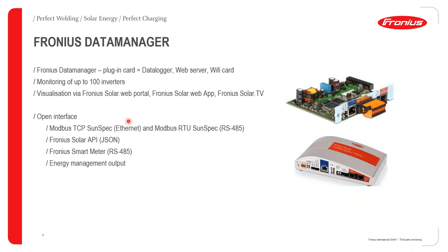These interfaces can communicate via the Fronius Solar API using the JSON protocol, communicate with the Fronius Smart Meter using the RS-485 protocol, and achieve energy management. The Data Manager can come integrated inside the inverter or as an external device in a box.